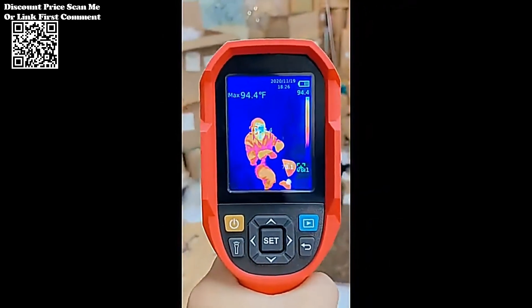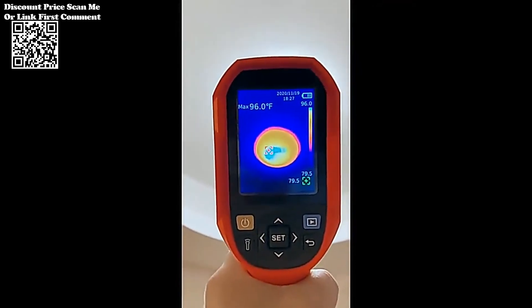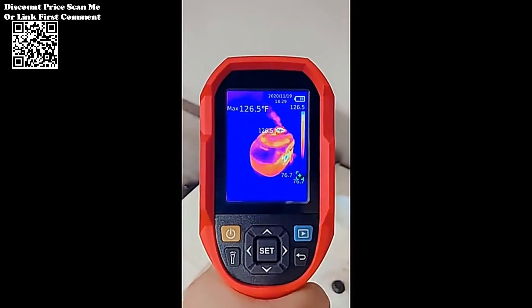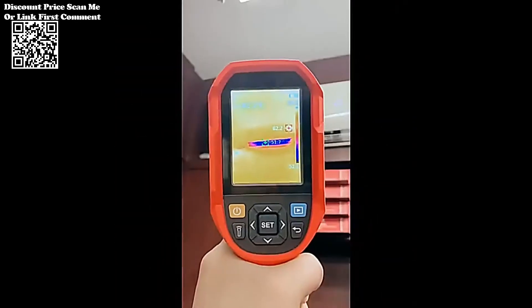The UNI-T UTi260B covers a broad temperature spectrum, ranging from minus 15°C to 550°C (5°F to 1022°F), making it suitable for diverse industrial applications including floor heating systems. It boasts an impressive accuracy level of plus or minus 2°C or plus or minus 2%, whichever is greater, ensuring reliable and precise temperature readings critical for maintenance and repair tasks.